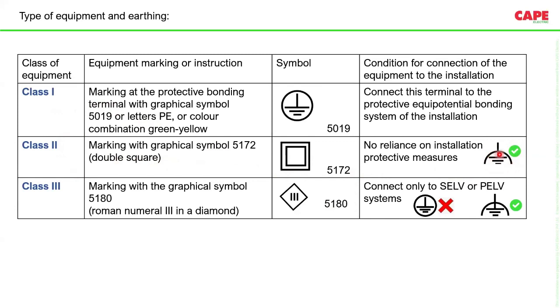Here on the right side, the symbol shows functional earthing. Class 3 devices are operating with a very low voltage, sometimes a voltage which cannot create a shock hazard. In this case also, protective earthing is not required, but functional earthing may be required. So whenever you make a protective equipotential bonding, first you should also consider the type of equipment which you are going to use. And for functional earthing, the recommended color is cream.